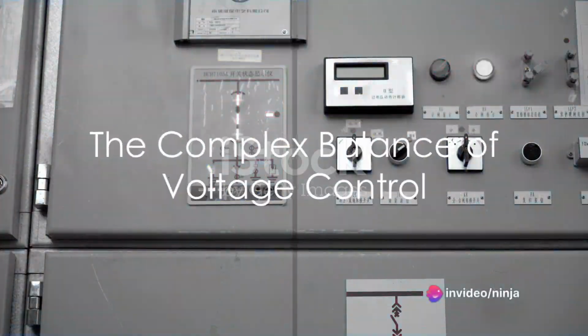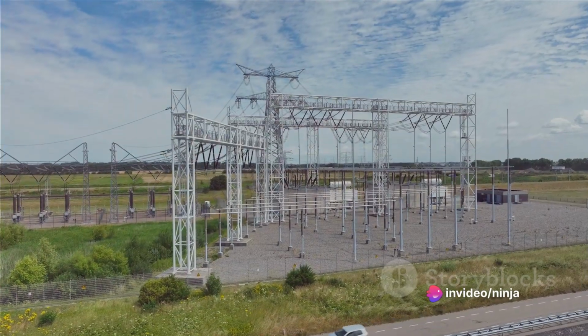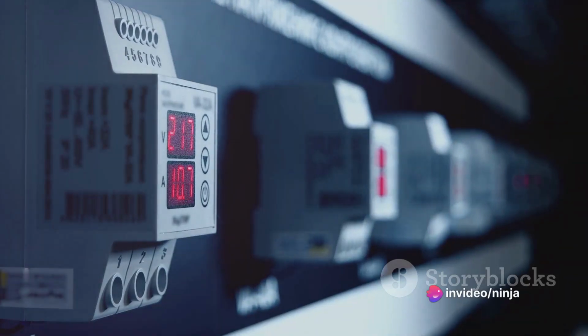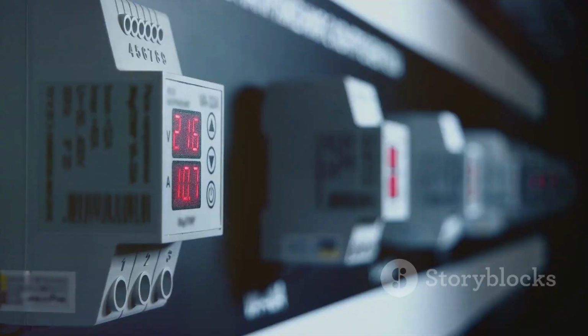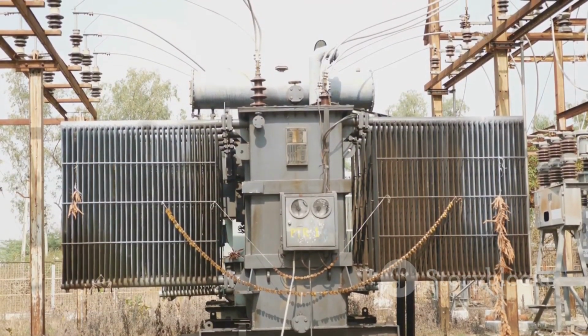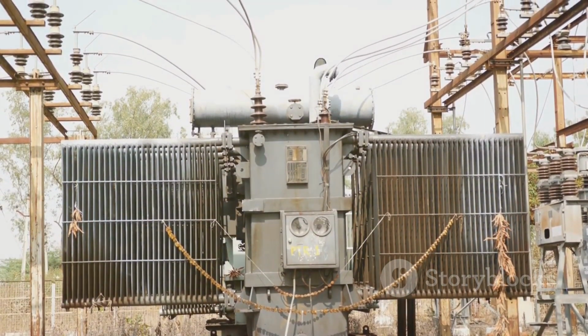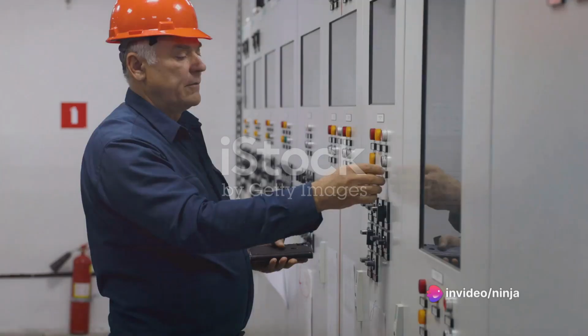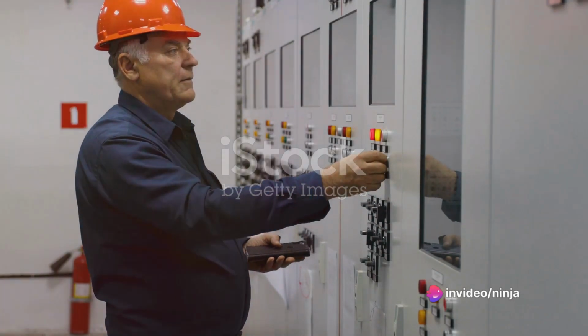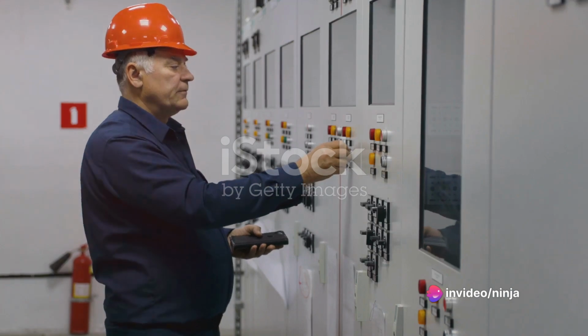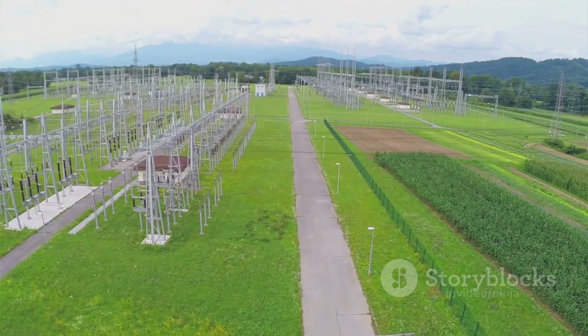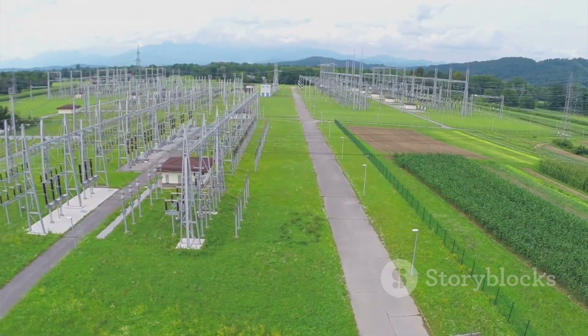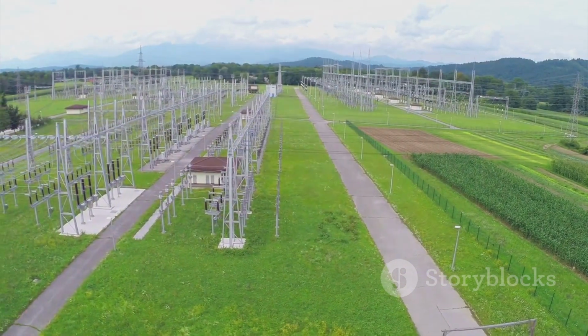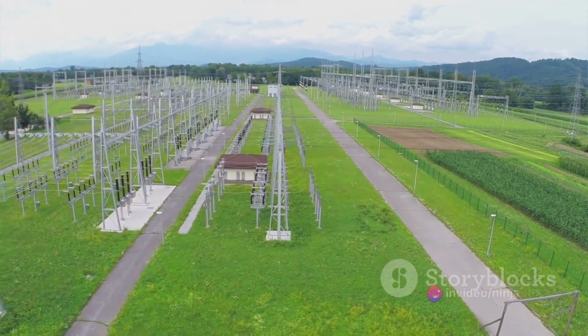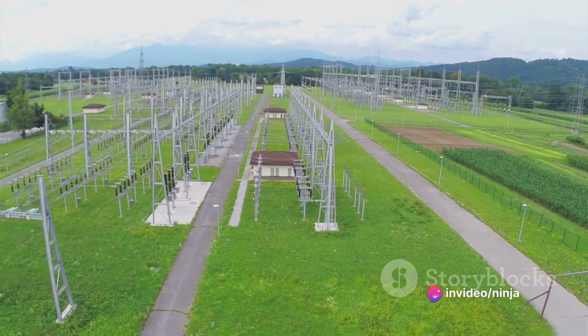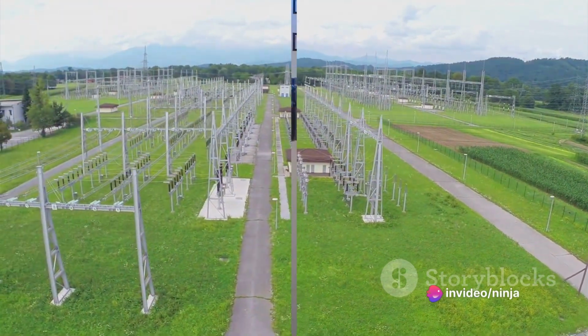To summarize, voltage control in a distribution network is a finely tuned balance. It involves the use of automatic tap changers and different turns ratios in transformers to keep voltage within a set deadband. It's a system that ensures the voltage supplied to both near and far customers remains within acceptable limits, regardless of load. However, the introduction of distributed generation is adding a new layer of complexity to this balance, potentially impacting the overvoltage margin and pushing the network beyond its hosting capacity.